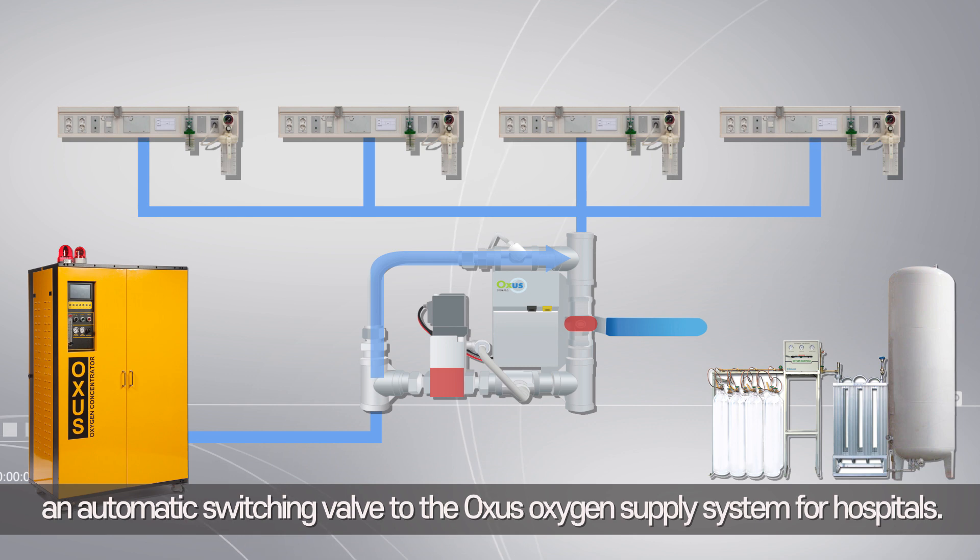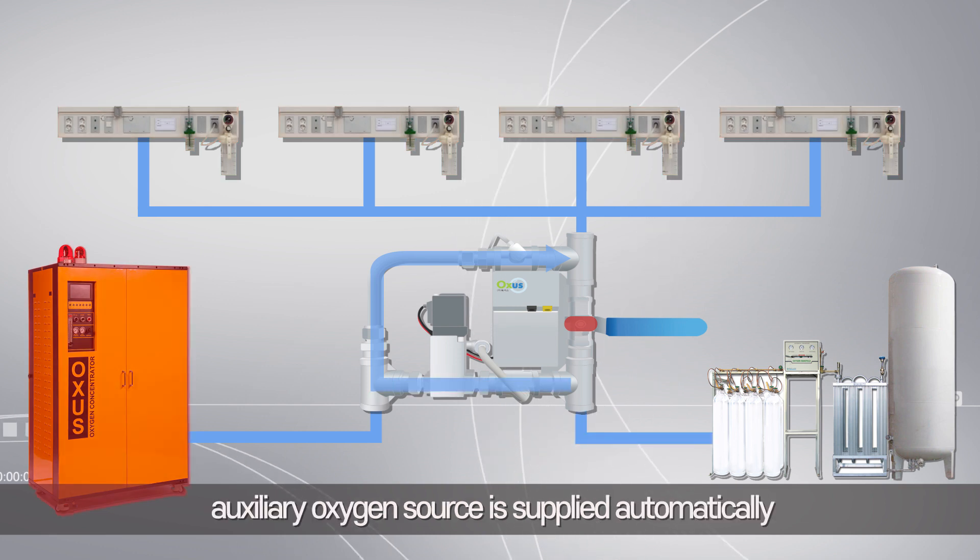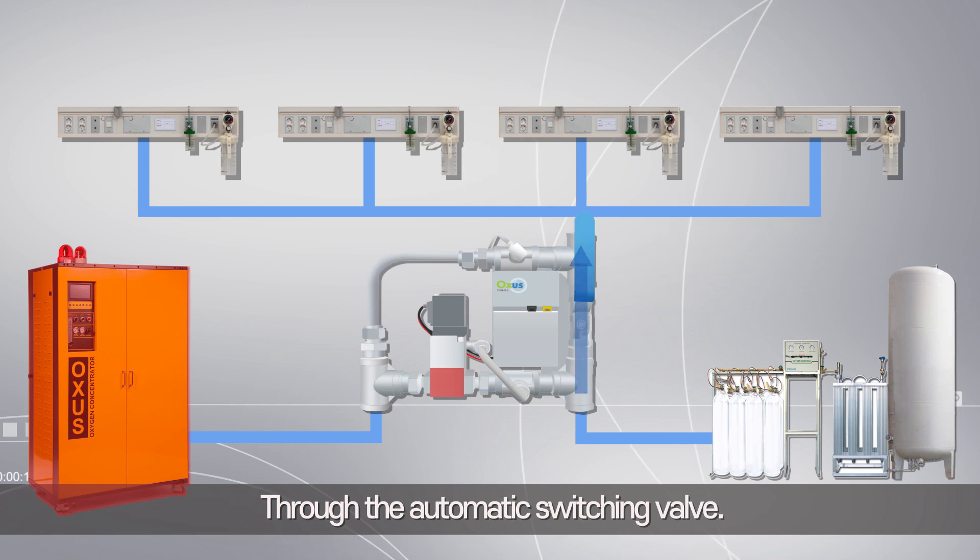You can choose to add an automatic switching valve to the Oxus oxygen supply system for hospitals. In case of emergency, an auxiliary oxygen source is supplied automatically through the automatic switching valve.